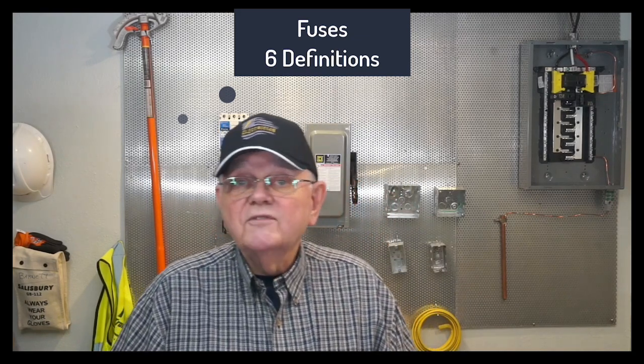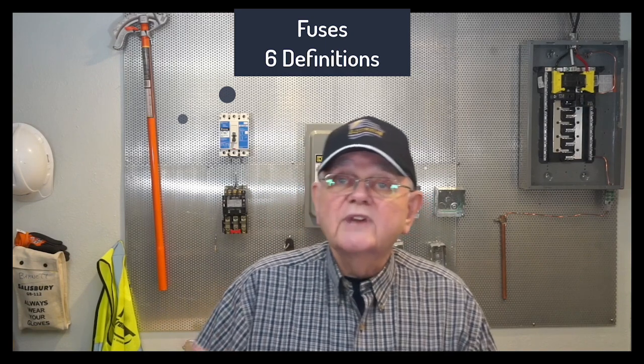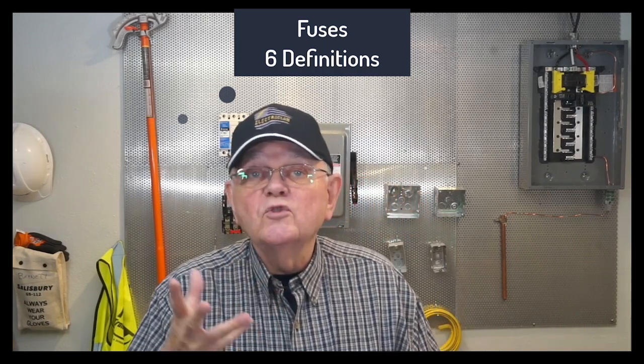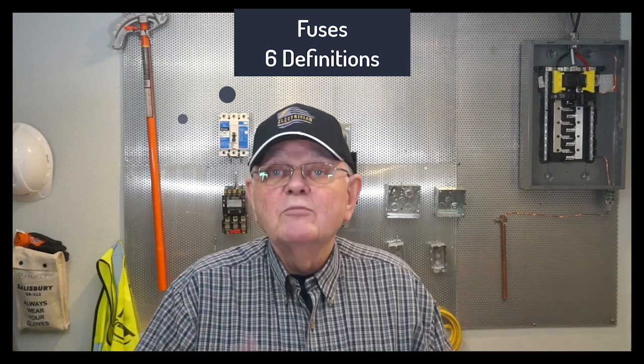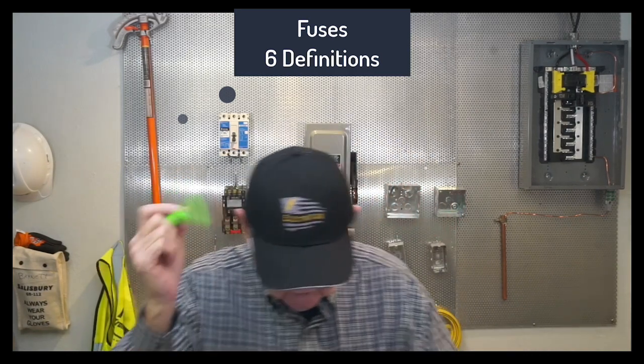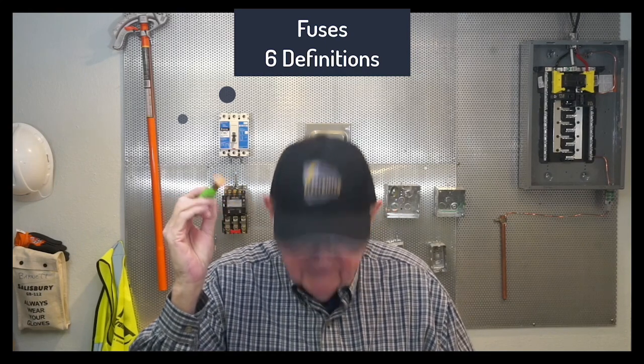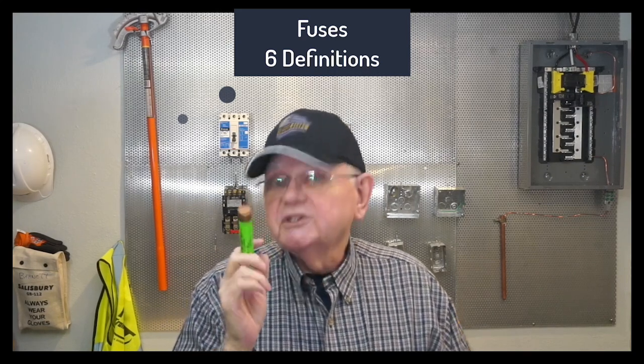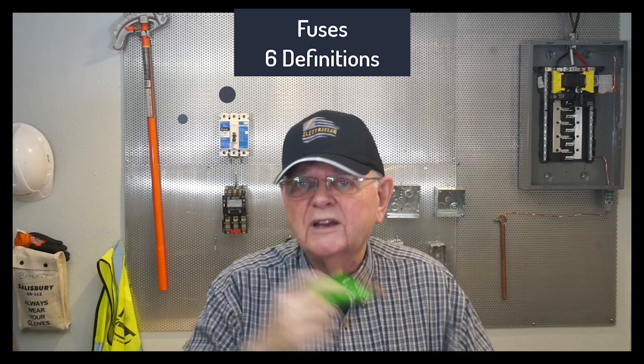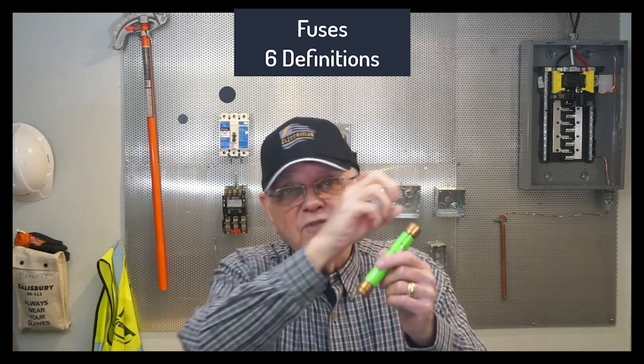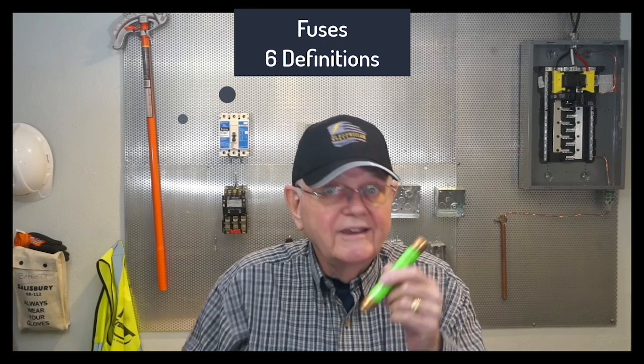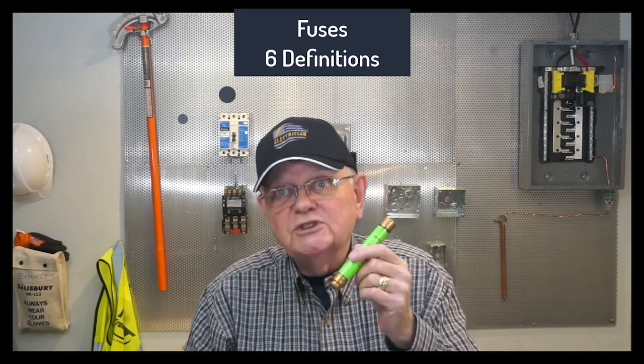Now let's talk about fuses. There are 6 different definitions of fuses. First of all, it's kind of nice, it gives us a definition for a fuse. It says it's an overcurrent protective device with a circuit opening fusible part that is heated and severed by the passage of overcurrent through it. So for instance, here's a power circuit fuse. There are electronically actuated fuses. There are expulsion type fuses that you'll see in your medium voltage systems up on a pole somewhere. And when the fuse blows, it actually forces gases out a hole in the bottom of the fuse. And when those gases come out, that's what actually extinguishes the arc on the inside.